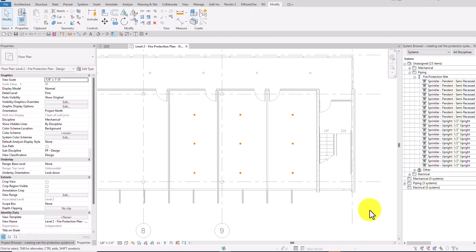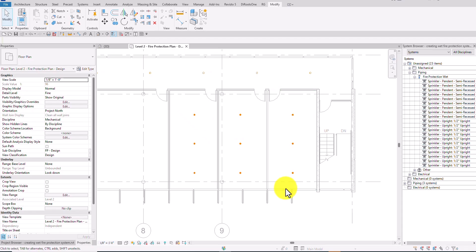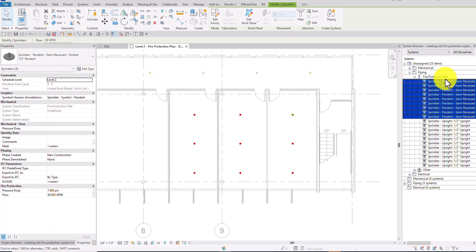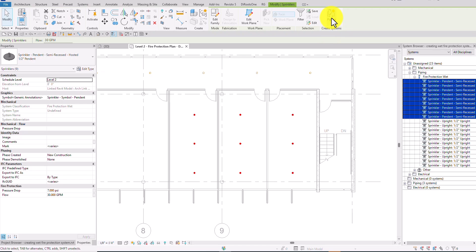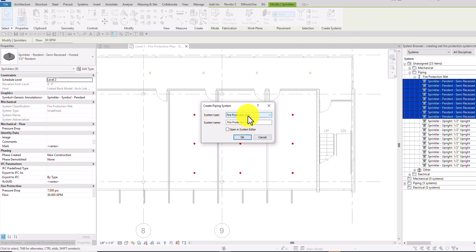They are all in the unassigned folder, so we're going to create a system to place them into our piping system. To do that, I'll select all the sprinklers — you can do it one by one, but let's select all of them. I have nine sprinklers selected, as shown by the filter. Over on the Create Systems panel there is a Piping option to create the system. The system type is fire protection wet.